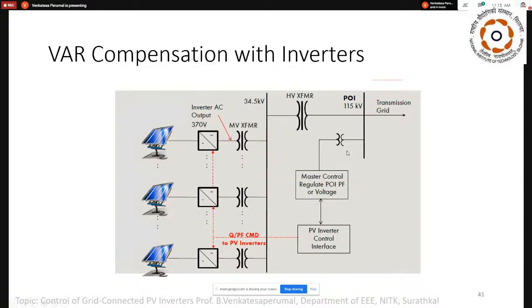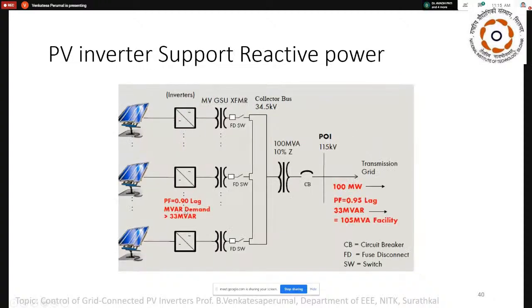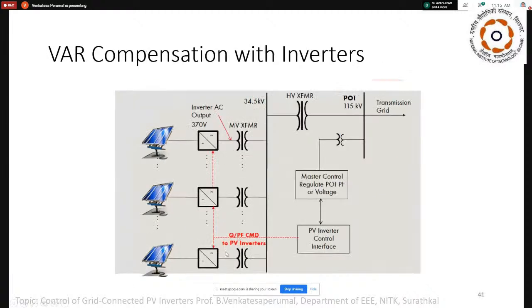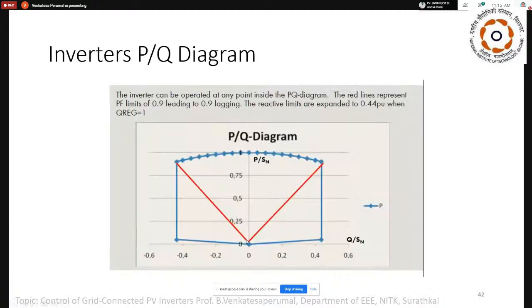Again, the P and Q command will come basically from the control loop. I can change the value. Previously it is set at 0.9, but it can be altered based on the conditions. How much is it going to support? You can see 0.45 on the negative side and 0.45 on the positive side. This is for the leading reactive power curve. So it can support 0.9 active power, and at the same time it can support 0.45 reactive power.